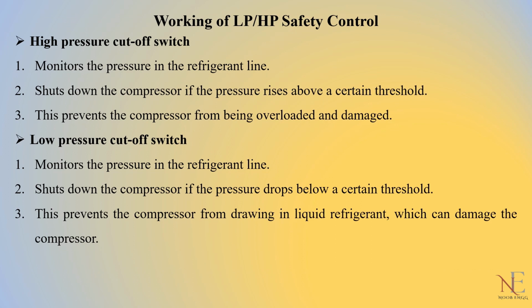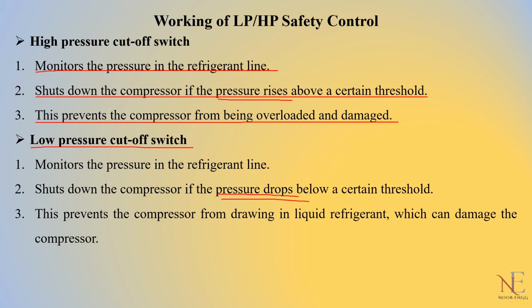Now let's move on to the working of these both. See here. The first one is the high pressure cutoff switch. It monitors the pressure in the refrigerant line and shuts down the compressor if the pressure rises above a certain threshold point. This prevents the compressor from being overloaded and damaged. And for the low pressure cutoff, only this line changes. Here it is a pressure drop, there it is a pressure rise, the rest are all the same. It's very simple. In low pressure, if the pressure drops, the compressor is off. And in high pressure, if the pressure is high, the compressor is off.